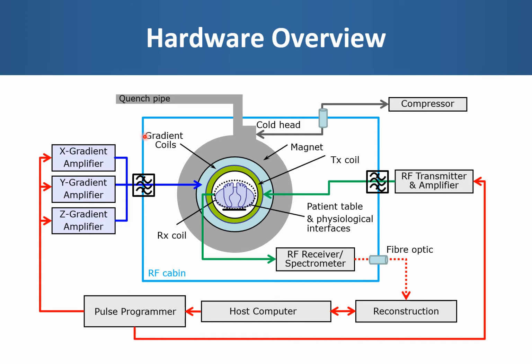I've mentioned this RF cabin several times and the waveguides that go through it. Because we are dealing with very small amplitude RF signals coming from the patient, we need to ensure that the system is isolated from any external radio frequencies which may overwhelm the small signal coming back from the patient. So therefore the scanner or the magnet is enclosed in a 6-sided metal cabin or box, sometimes called a Faraday cage, that isolates the sensitive electronics inside from any external radio frequencies. And it also means that the high energy radio frequency pulses that we generate as part of the imaging process cannot leak out and interfere with potentially adjacent MRI scanners.